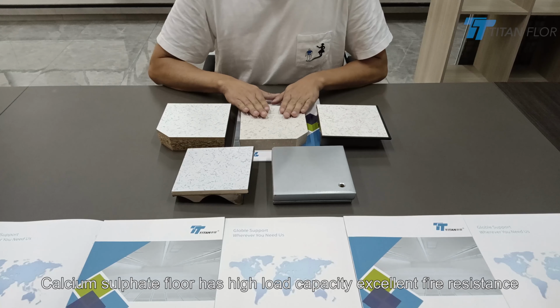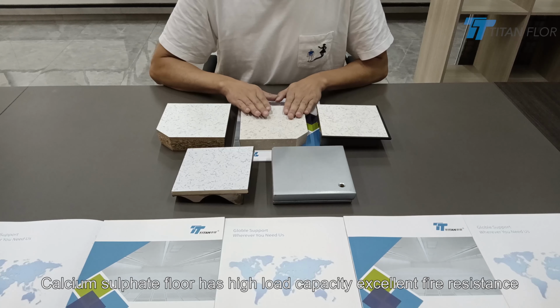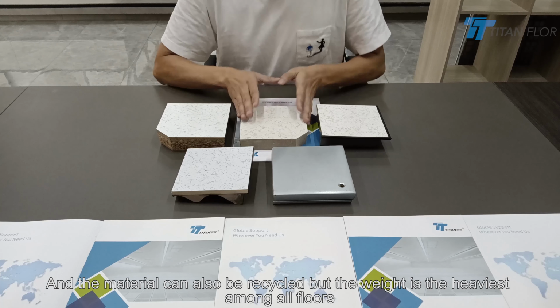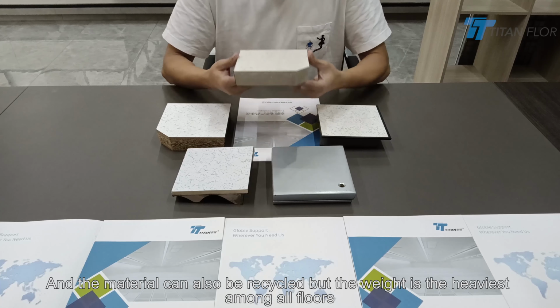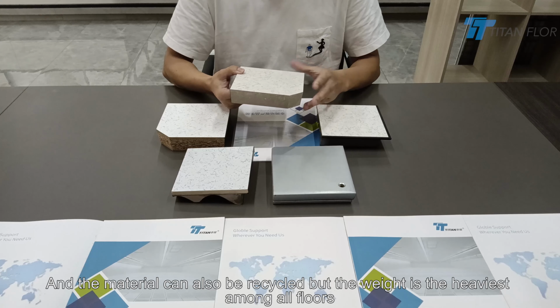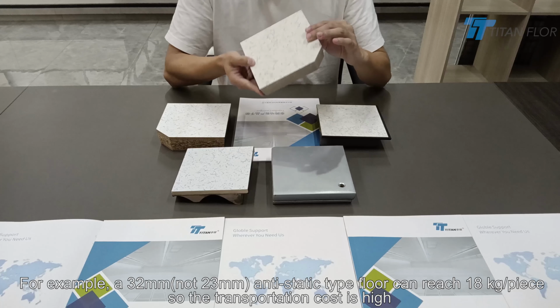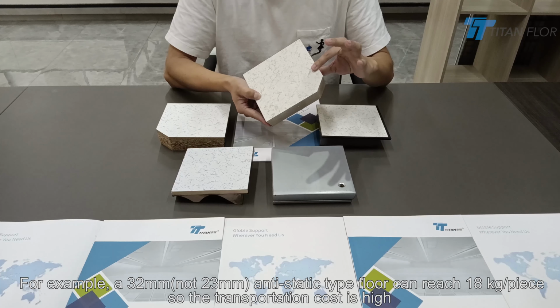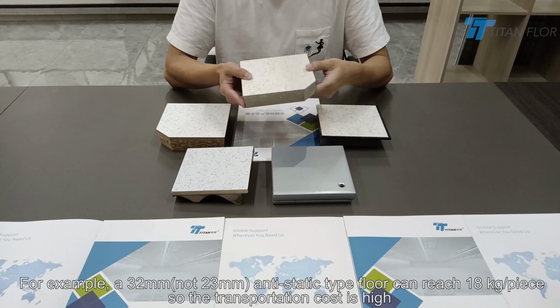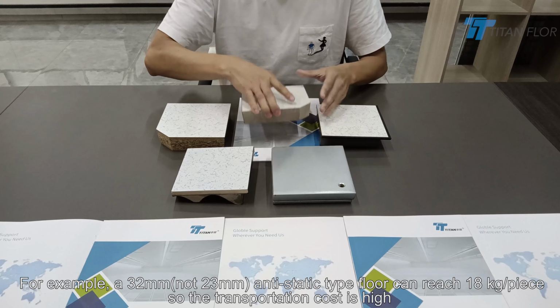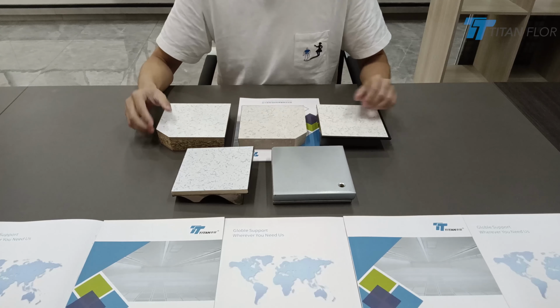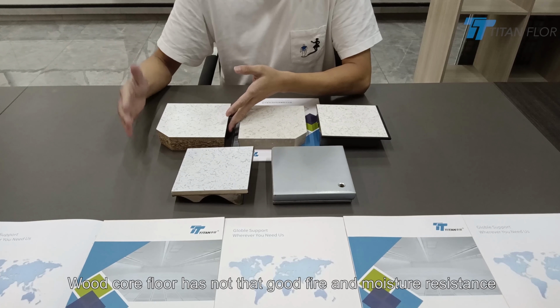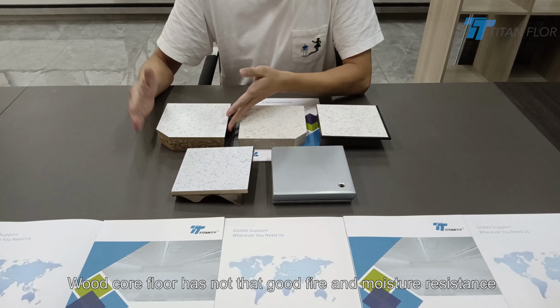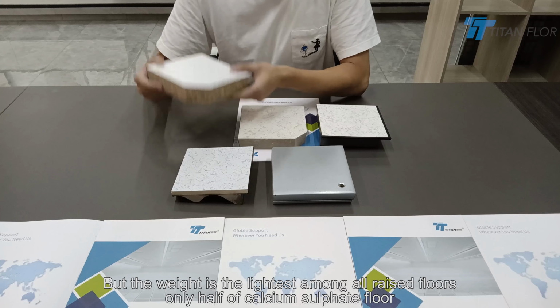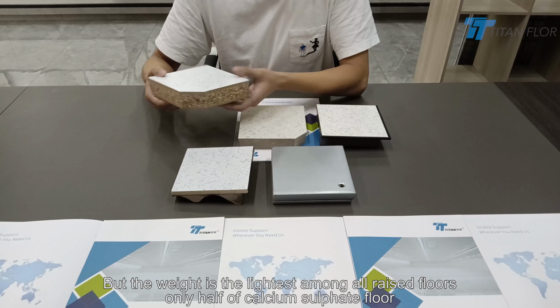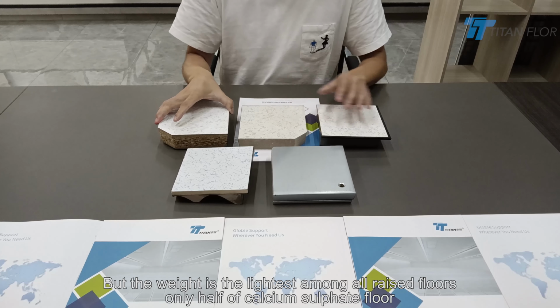Calcium sulphate floor has high load capacity, excellent fire resistance, and the material can also be recycled, but the weight is the heaviest among all floors. For example, a 32mm anti-static type floor can reach 18 kilograms each piece, so the transportation cost is high. Wood core floor has not that good fire and moisture resistance, but the weight is the lightest among all raised floors, only half of calcium sulphate floor.